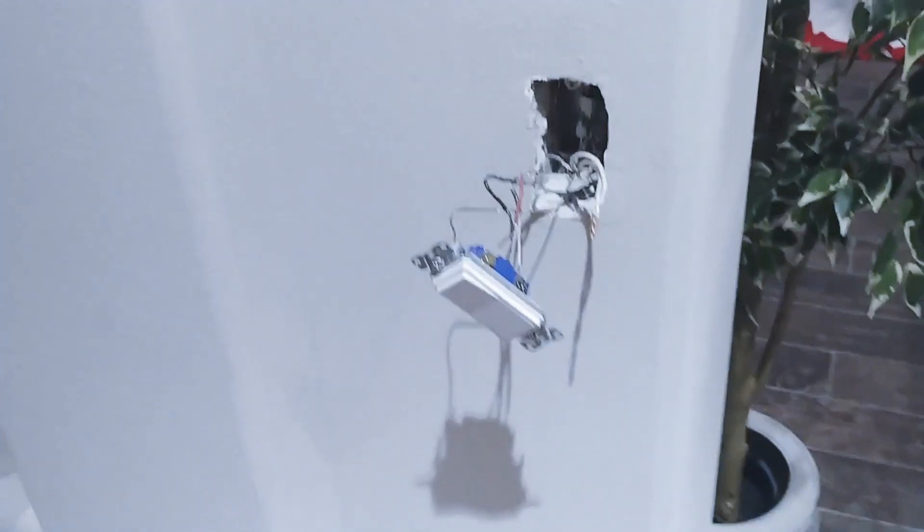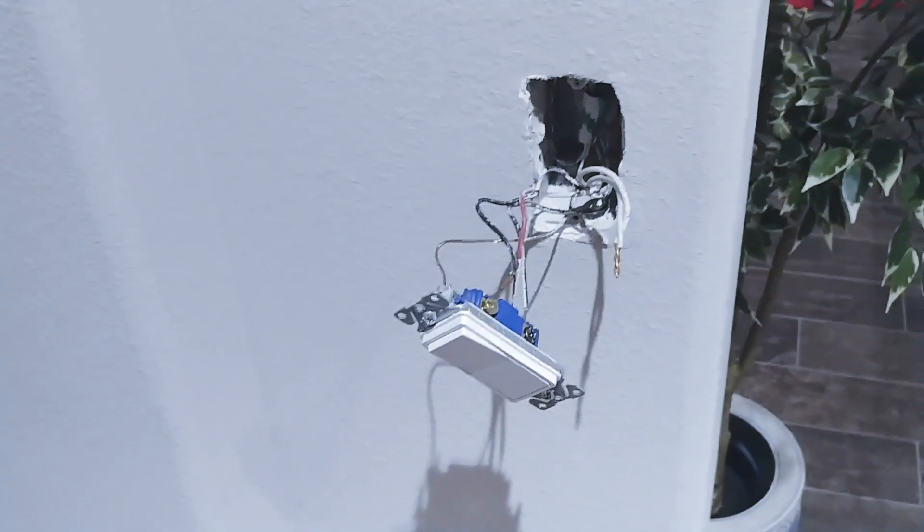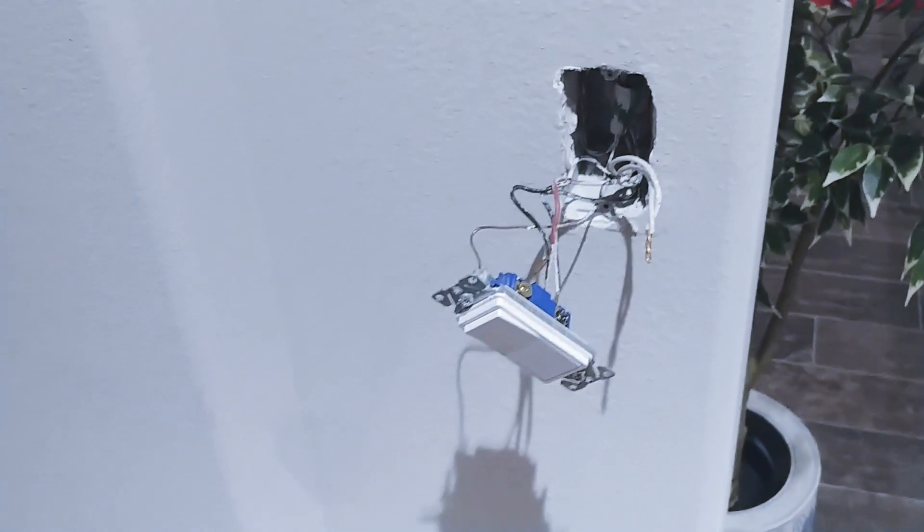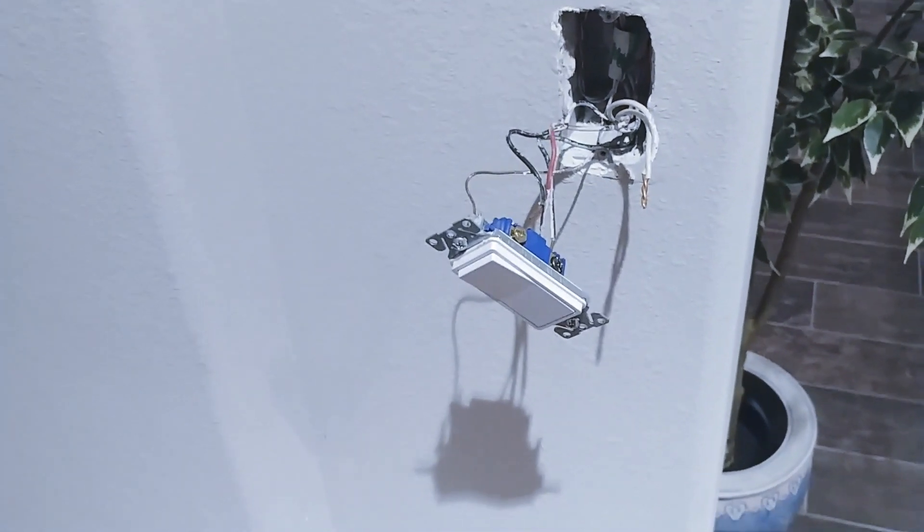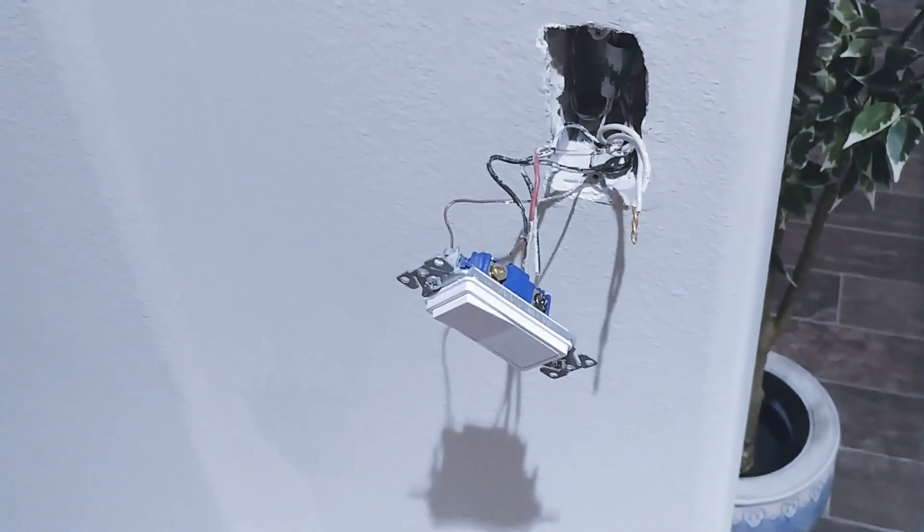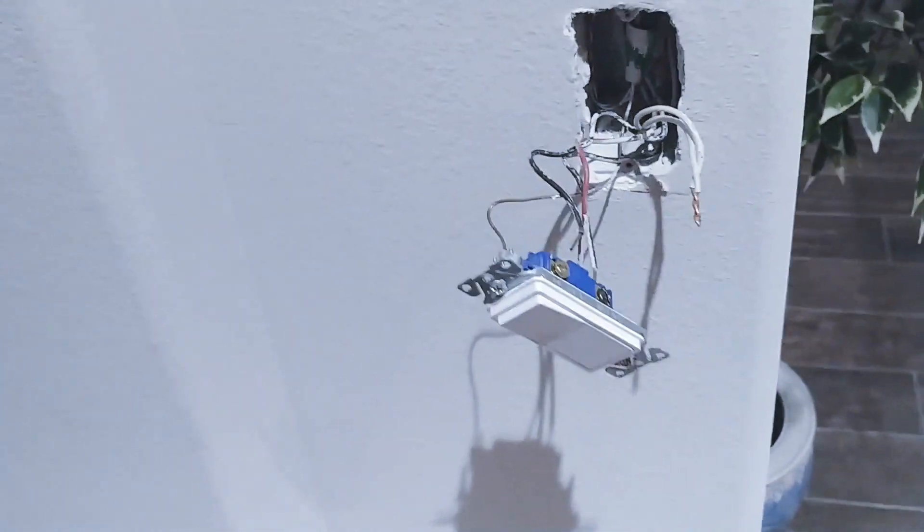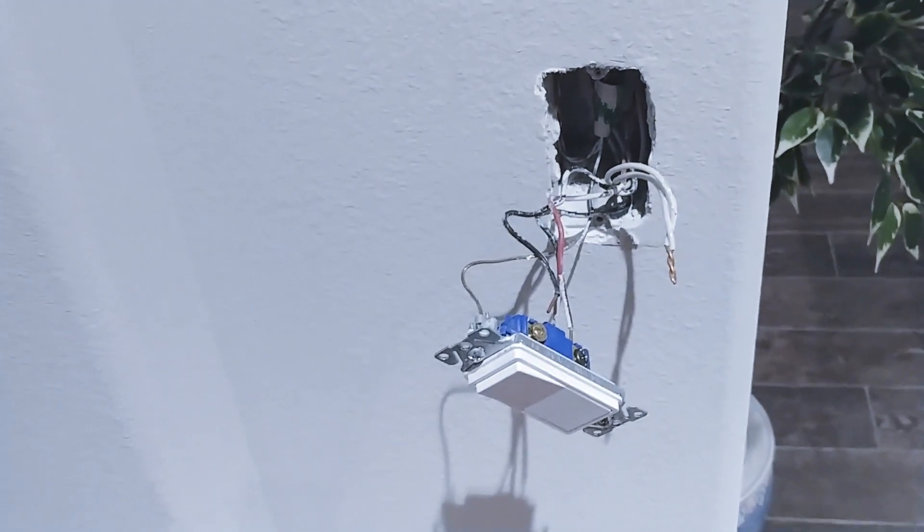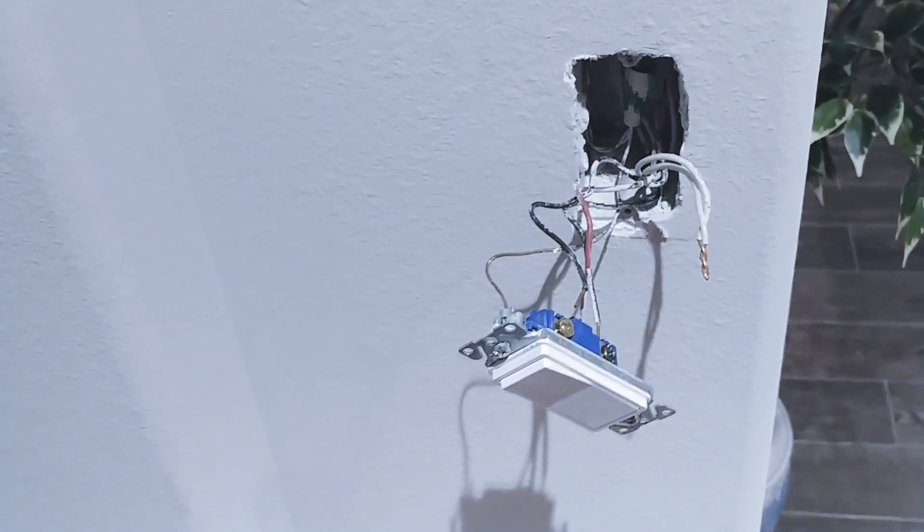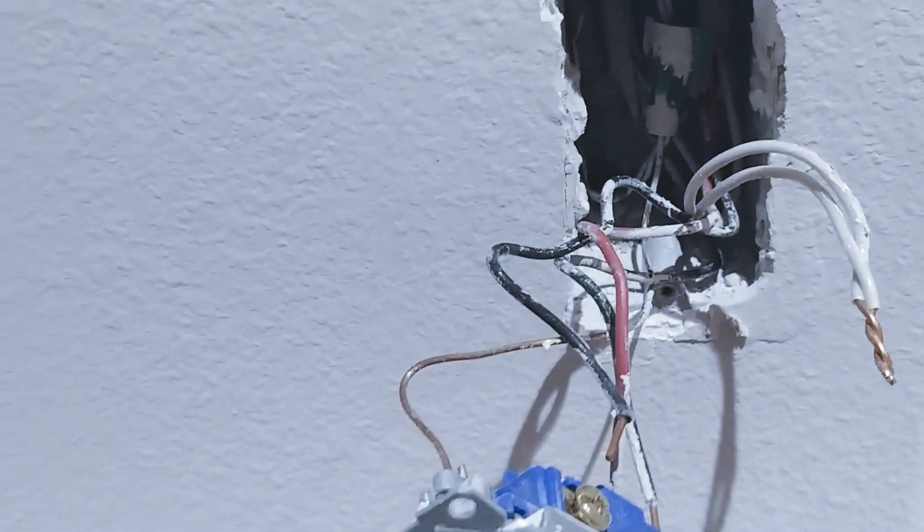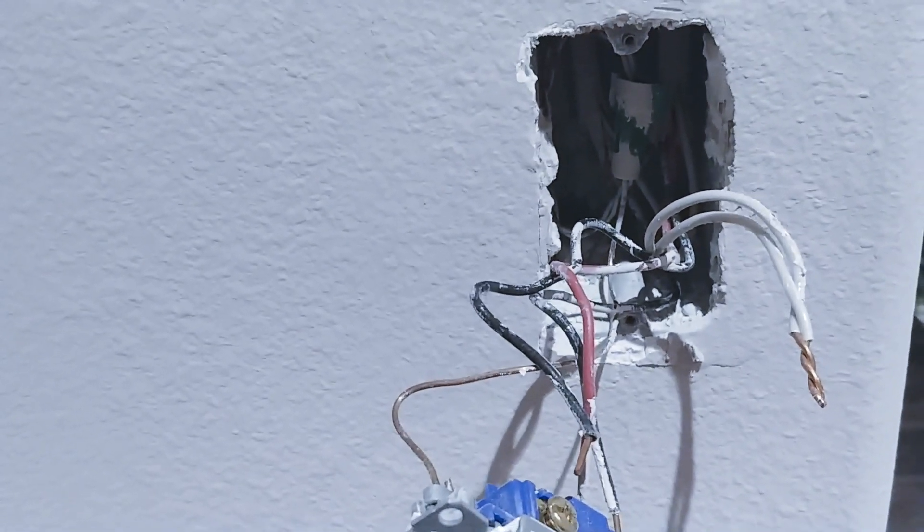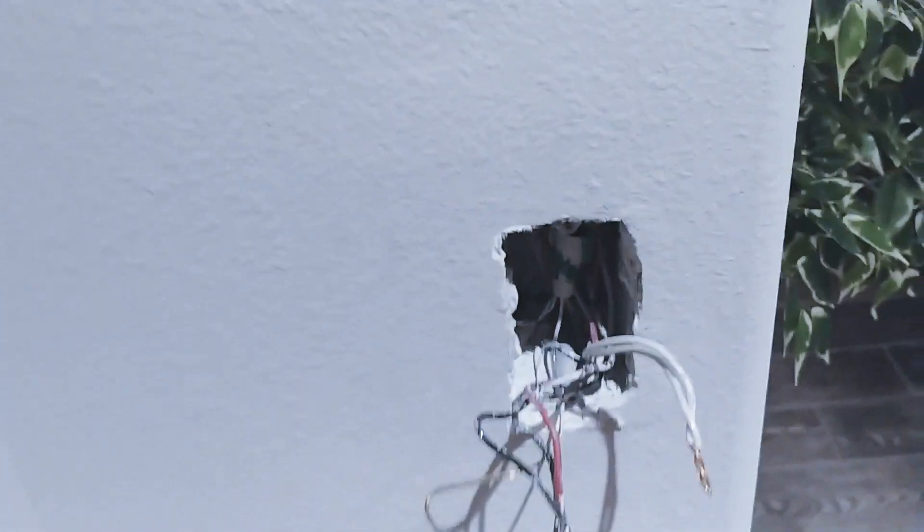So here's my switches and one of the things I've done is I turned the power back on just so we can see, otherwise it would be too dark. Those wires are alive and I don't want to touch them right now. But one thing I do want to show you is I'm pretty sure this is the load and this is the one I have to put my four-way switch on. The reason I can tell is if you look up in there you can see the wires are pointing up. So that's a very telling sign because the wires pointing down, my load which is my light is in the ceiling, that wouldn't make much sense for the wire to be pointing down.